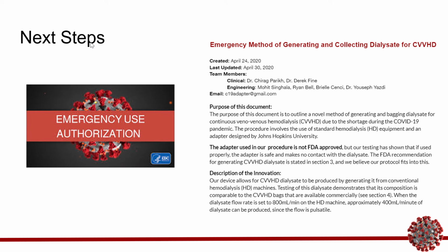We are making our process and adapter open source so that any hospital in need can utilize our solution. We have created a document that explains how to 3D print an adapter and how to perform the dialysate generation process. We are currently looking for more avenues to disseminate this document to reach those in need of making dialysate. Since the process and adapter have not yet been added to the EUA, our document also includes our testing protocols that we believe hospitals should perform before clinical use to ensure that the dialysate they're producing is safe. We have modeled this process and testing plan off of the FDA's general guidelines for creating dialysate during this crisis. Additionally, we plan to continue testing so that the process can soon be added to the EUA.